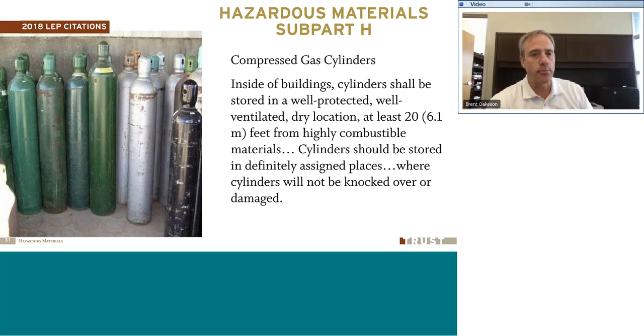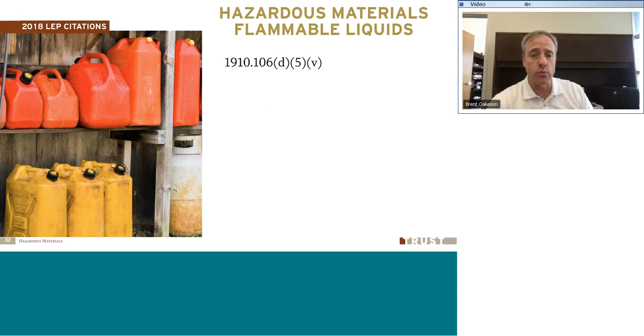We also need to make sure these cylinders are separated so we don't have flammables and oxidizers close together. The most common example is oxygen and acetylene. If you have any fuel gas stored under pressure and an oxidizer like chlorine or oxygen stored under pressure, those cylinders need to be at least 20 feet apart as a general rule. You can also engineer a fire break between them if they need to be close together, but the most common approach is just to separate them by 20 feet. Another citation we saw quite a few of was storage of flammable liquids.